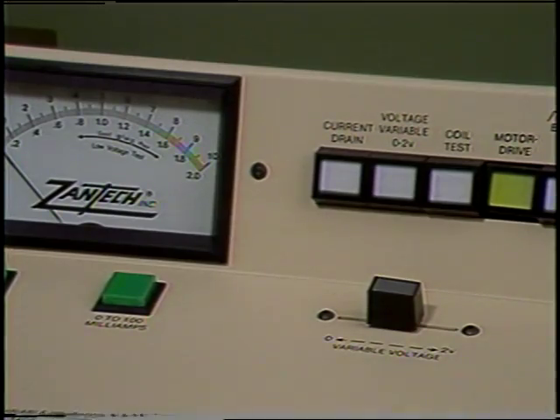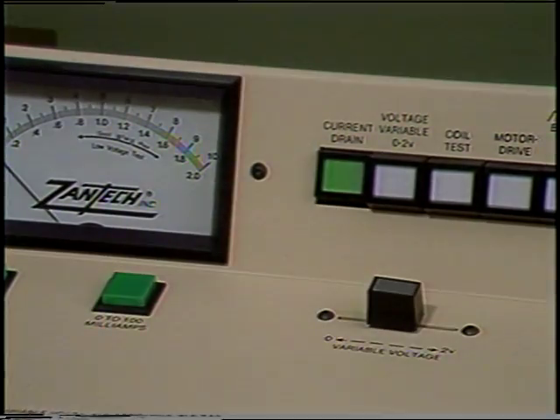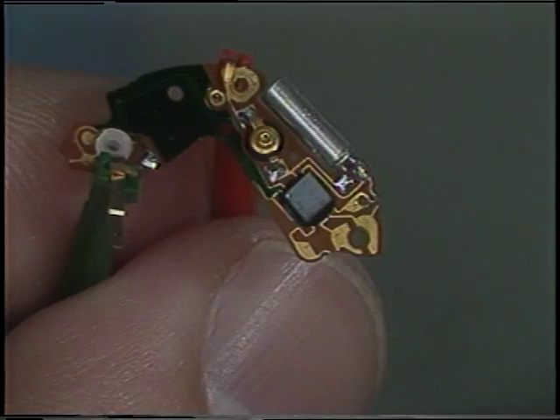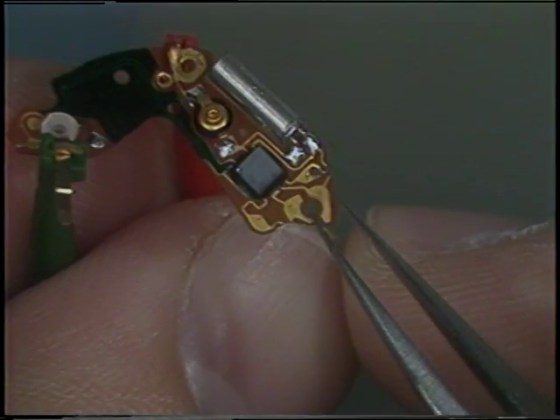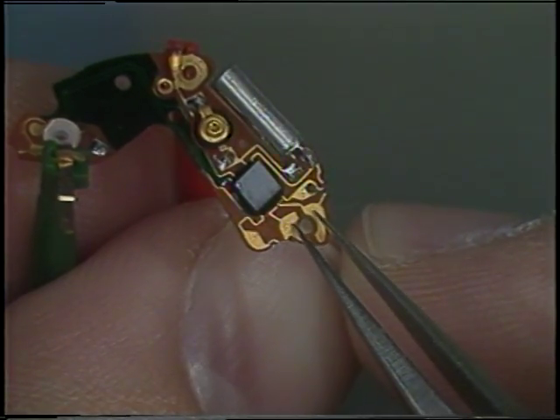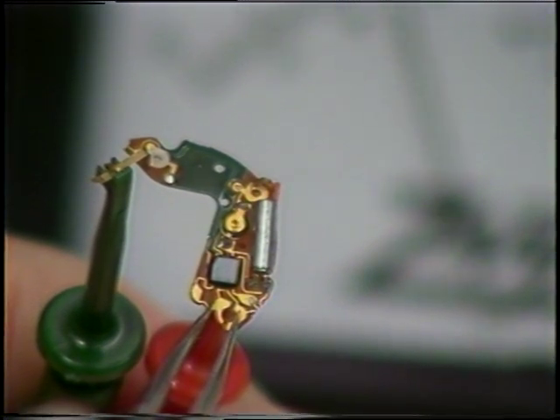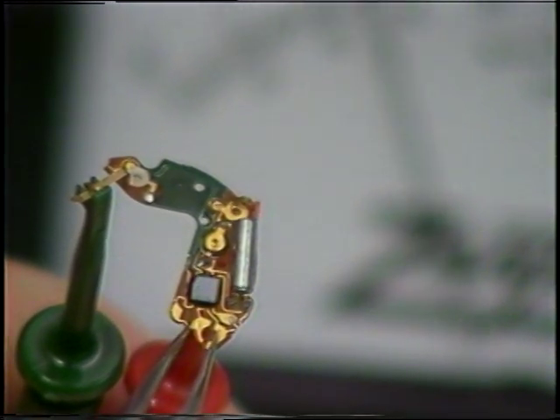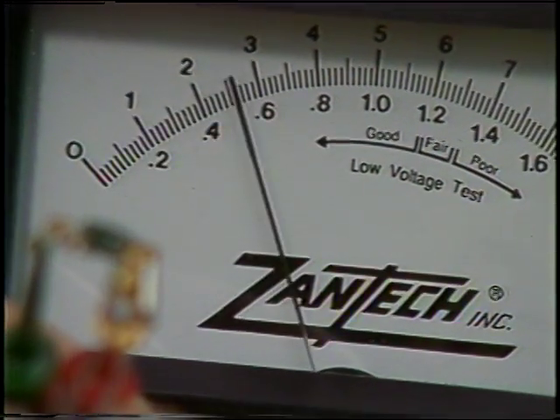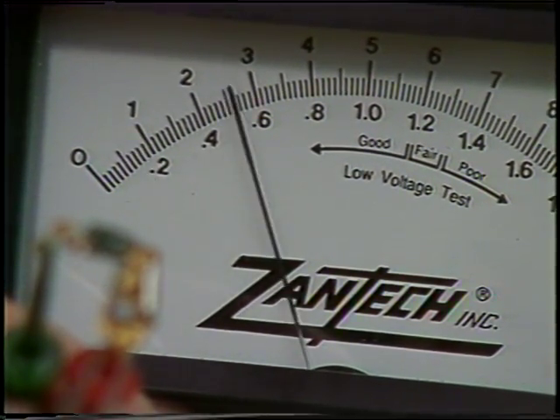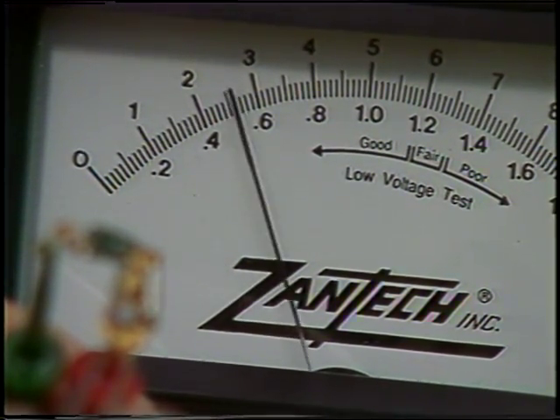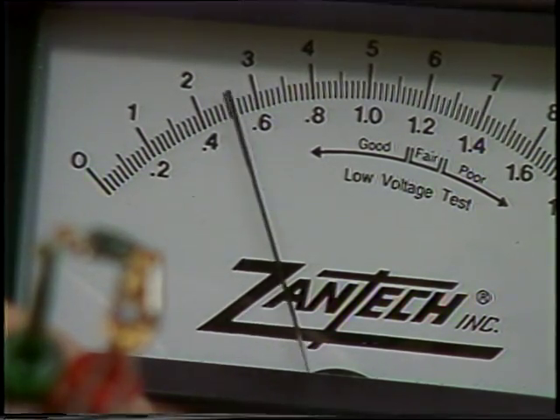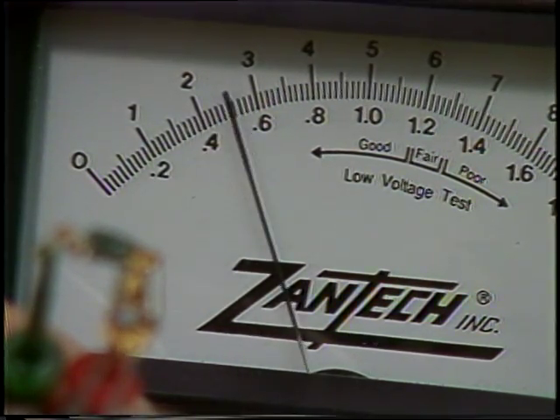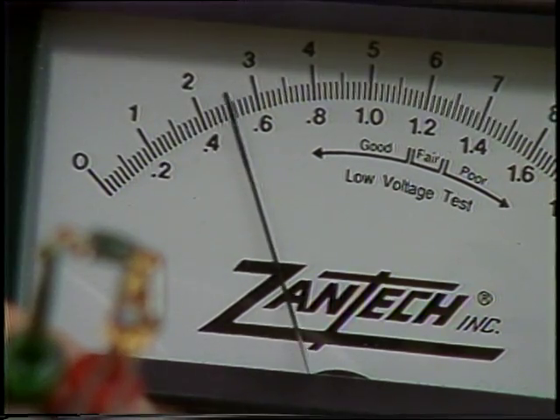Push in the current button. When a normal current reading is obtained, short-circuit the 2 coil contact pads on the circuit board with a pair of tweezers. The short across the coil contact pads represents a substitute for the coil. If the circuit board is good, the analyzer will begin to click each time the circuit board sends a pulse through the tweezer, just as if a good coil were connected to the circuit board.